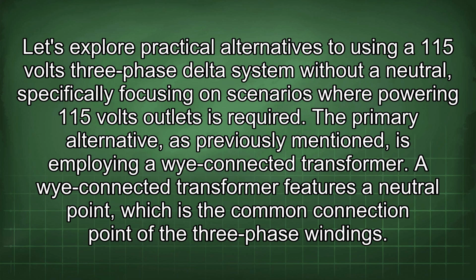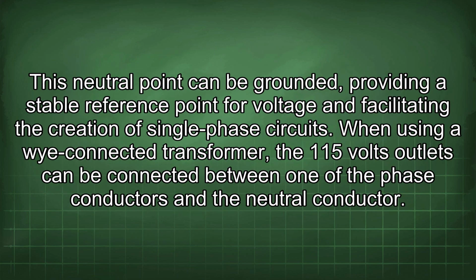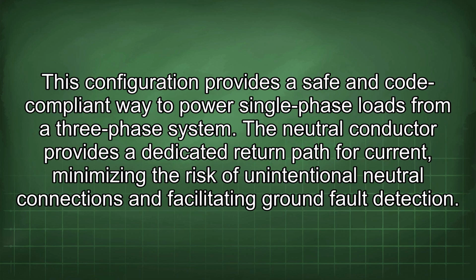The primary alternative, as previously mentioned, is employing a Y-connected transformer. A Y-connected transformer features a neutral point, which is the common connection point of the three-phase windings. This neutral point can be grounded, providing a stable reference point for voltage and facilitating the creation of single-phase circuits. When using a Y-connected transformer, the 115 volts outlets can be connected between one of the phase conductors and the neutral conductor. This configuration provides a safe and code-compliant way to power single-phase loads from a three-phase system.